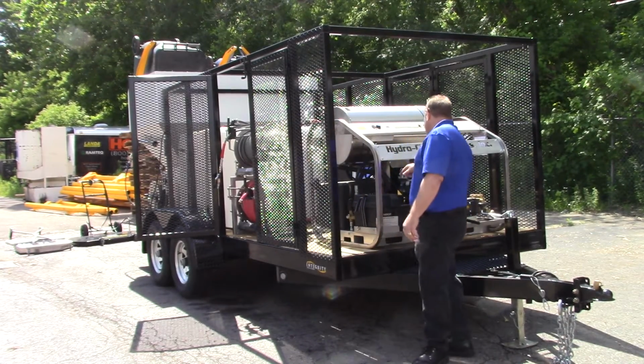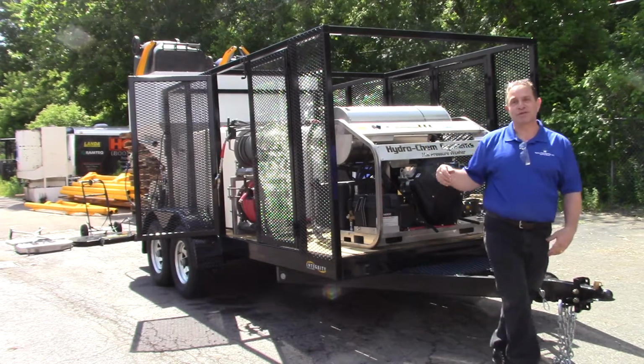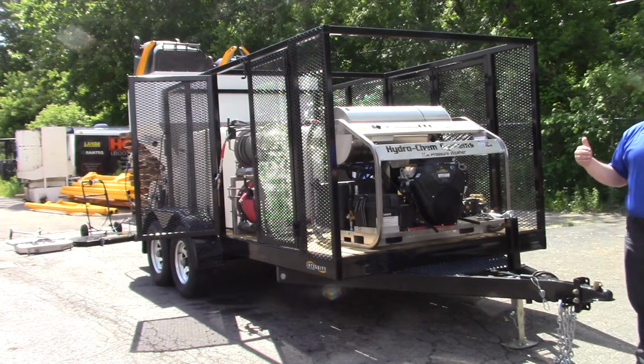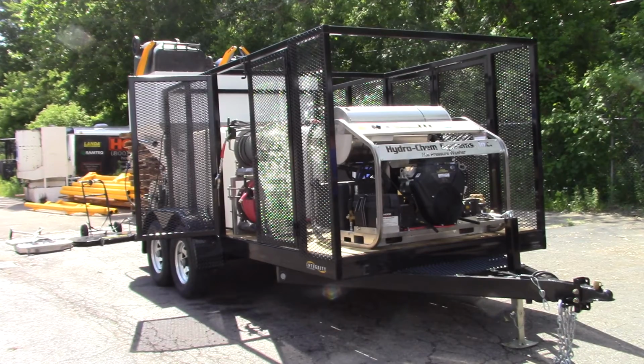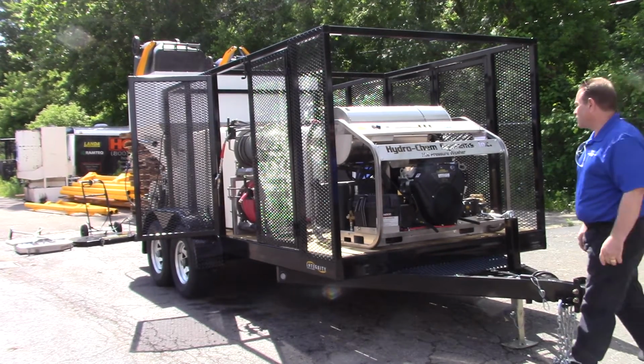It's a new model, it's somewhere around here, but there's a pressure switch, a micro switch, that also is the redundant safety device. So now we've got no pressure, no heat, no flow, no heat. Too much heat, it's going to cut off with the thermostat control.